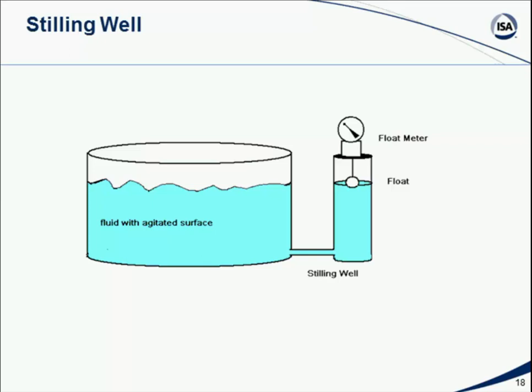Now again, this drawing's a bit simplistic. In most cases, you'll see that a stilling well is actually a pipe inserted into the tank itself, somewhere off to the side, but in the tank. It's usually not built as a separate entity. But the concept of having a separate protected vertical column where the fluid can only come in from the bottom, and thus we avoid the fluid surface agitation problem, is common to the way we make use of stilling wells. So if you're going to use a float tape system, you probably will use some type of stilling well to make sure you can get an accurate measurement.